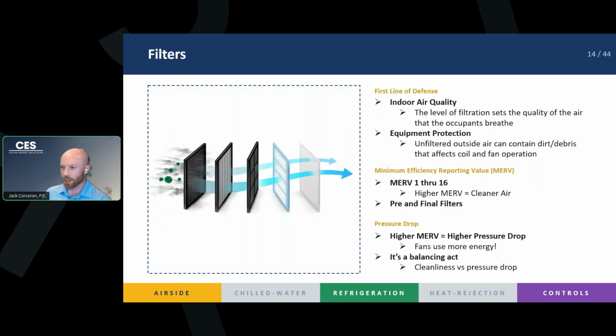So following our airflow through the unit, the next thing it'll hit is your filters, right? These are very important. Not only do these act as the first line of defense for the air quality of the occupied space, it also protects your equipment, right? So if you have high efficiency filters, you're going to have very, very high quality indoor air, right? There's not going to be a lot of particulates or bacteria. All of that is going to be stopped at the filter, and then you switch them out and change them every few months so that bacteria, that dirt, that debris never actually gets into the space. So it's clean air in the space for the indoor air quality, and also you don't get any dirt or debris that gets on your cooling coils or gunks up your fan. All of that affects the efficiency of those pieces of equipment. And if we can stick those filters in there, they do two things at once: they make your indoor air high quality and clean, and they also protect your equipment in the packaged unit.